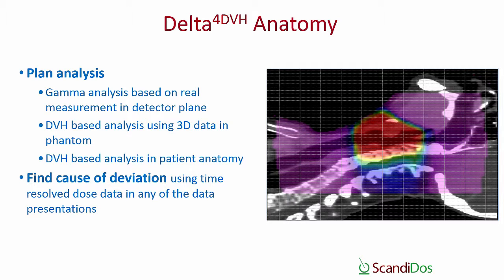And in the Delta4 system, we measure the dose distribution per pulse, each dose pulse individually, with very, very high accuracy. So the complete electronics is made to measure the dose per pulse, and thereby the accuracy is better than 1% in dose detection per pulse. And this gives you the possibility to look into the detailed data and find the cause of the discrepancy.